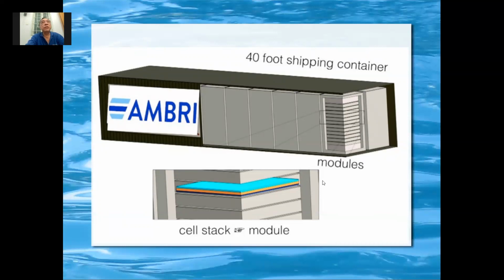Sometimes people worry about the temperature, but to him it's not an issue, because as the battery runs day and night, the temperature will maintain itself. It's not unlike lithium, where you worry about, wow, too hot. The lithium battery will burn and damage the whole battery. But this one, hot, never mind. Too hot also never mind, because it just melts. It's molten metal, so they are not afraid of heat. They are more afraid of not enough heat. Then the metal becomes solid, then it stops working. So it's a different worry.